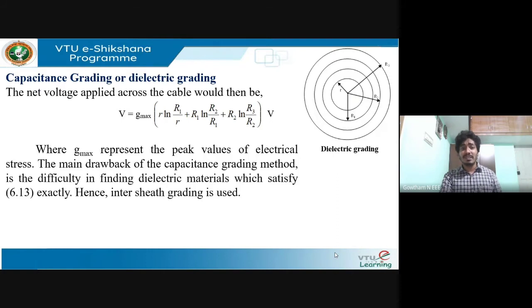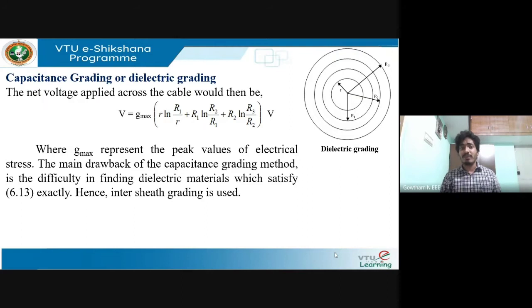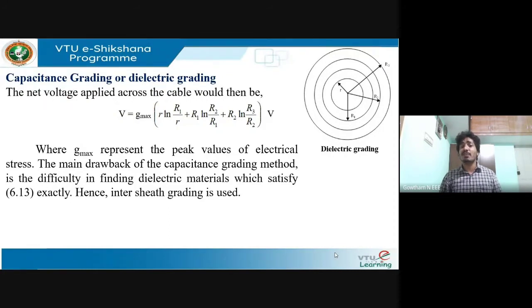Here, g_max represents the peak values of electrical stress. The main drawback of capacitance grading is finding suitable dielectric materials — it is very difficult to identify materials with the required permittivity values to achieve proper grading. Because of this drawback, inter-sheath grading is more widely used.